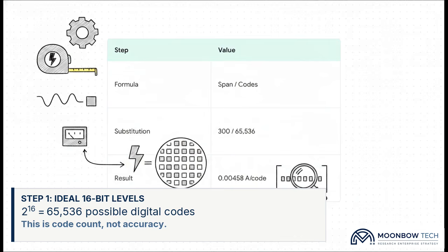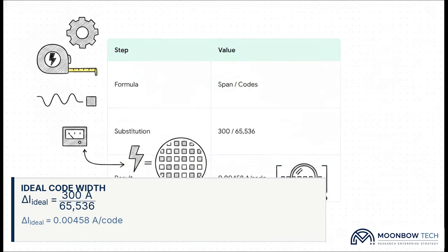Next, we need to find our LSB size, our ideal code width. The formula is our span divided by our total codes. So we take our required 300 amp span and divide it by those 65,536 codes. The result is 0.00458 amps per ideal code. That right there is the smallest theoretical step our instrument can take.